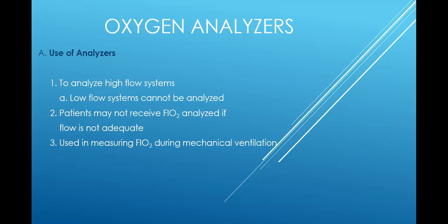All right, now we're on the oxygen analyzer, which is the last part of this lecture. Oxygen analyzers. Oxygen analyzers are little devices that are used to measure the FiO2 of the device. If I have a device that is blowing, right?